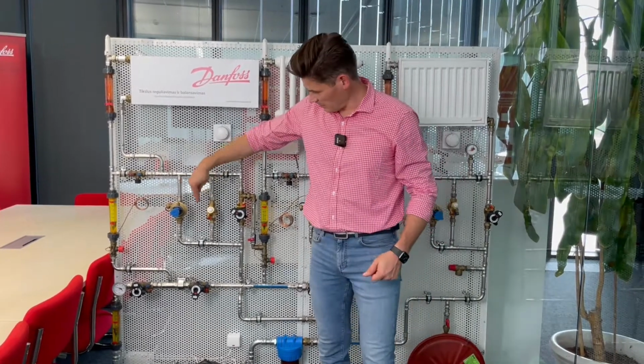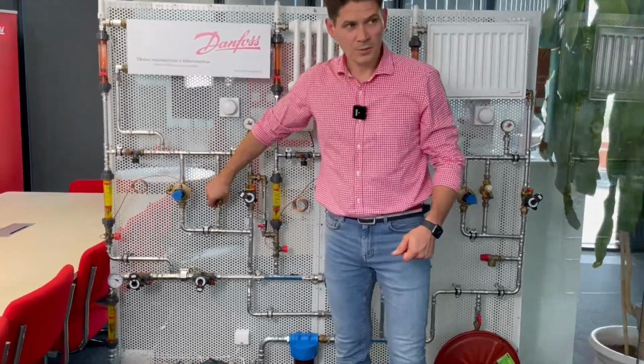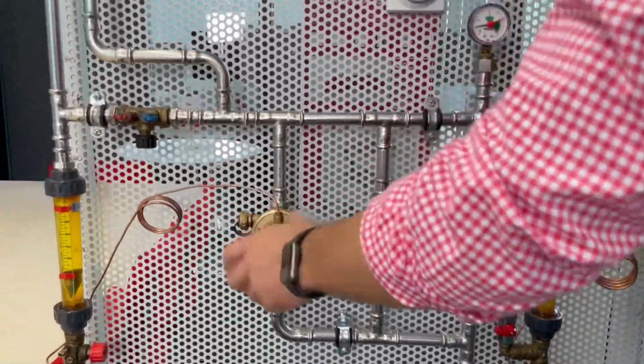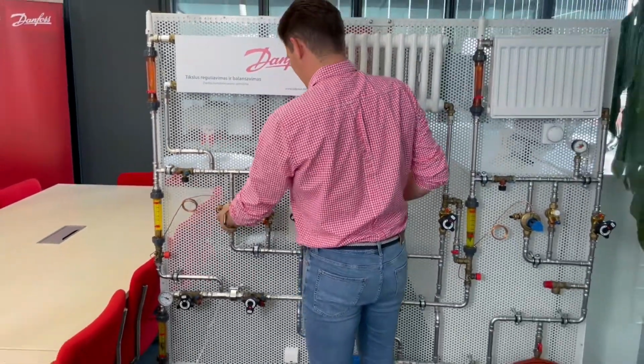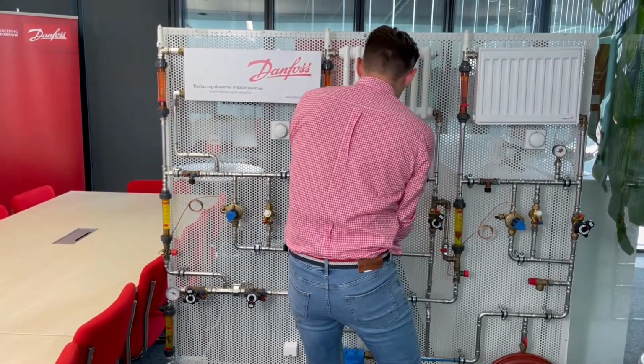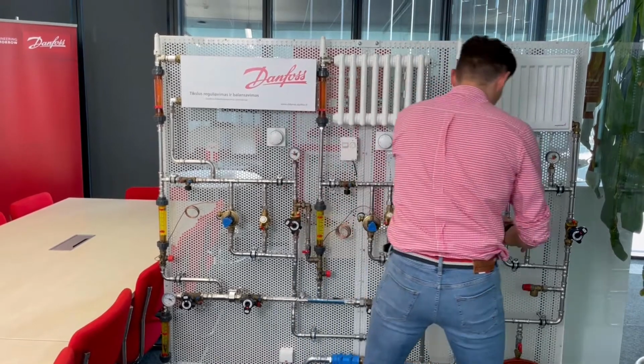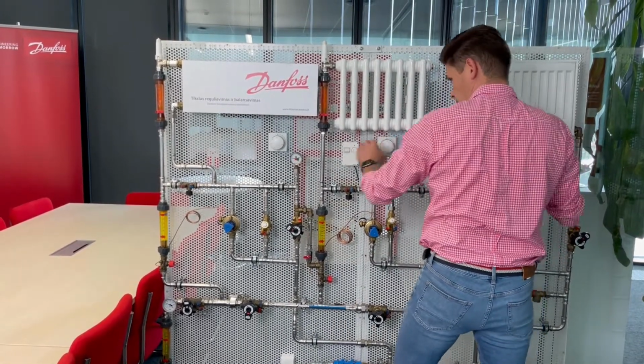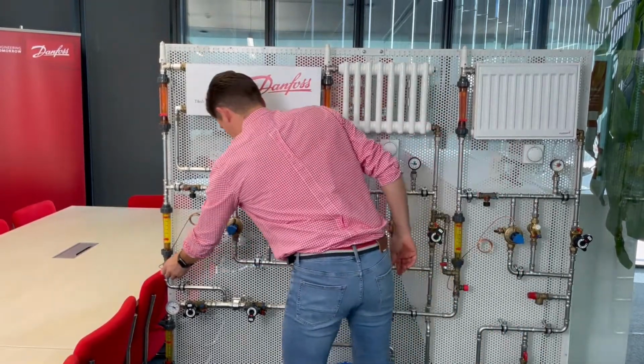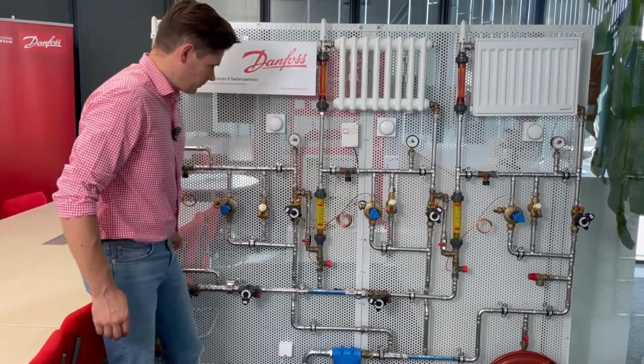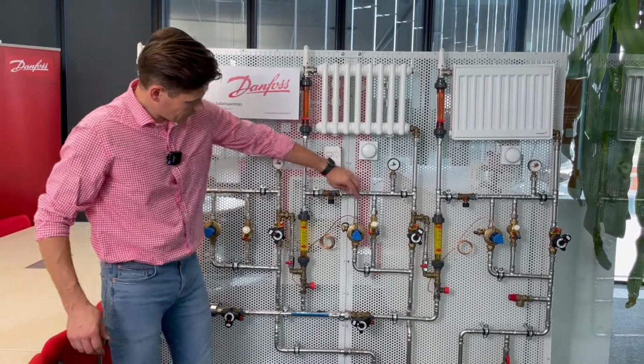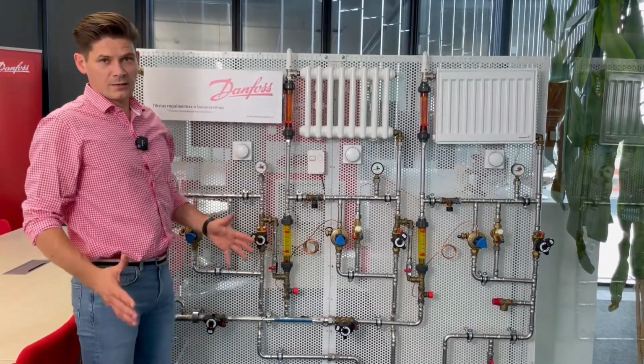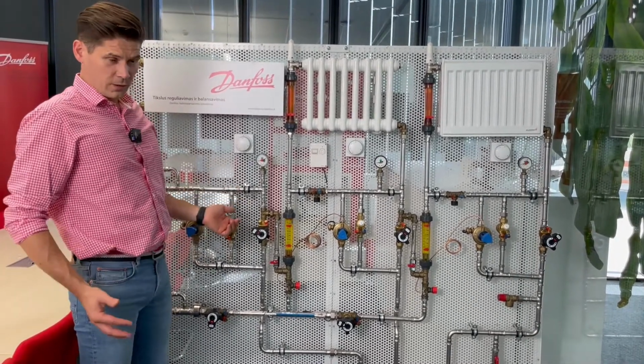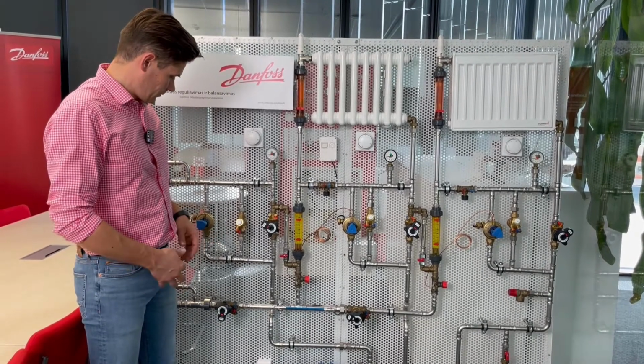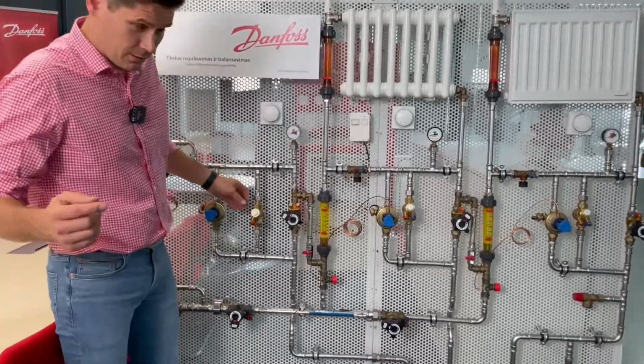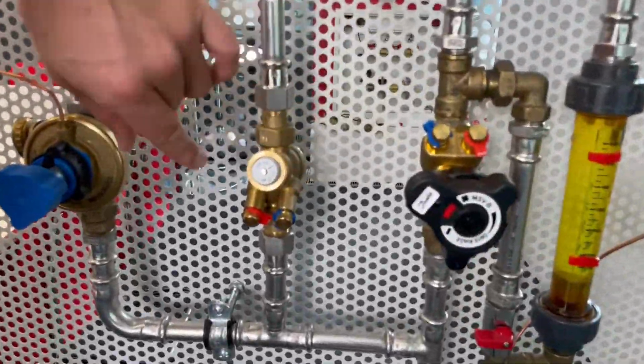Okay, the last automatic balancing valve is the ABQM, a pressure independent balancing and control valve. So I closed the pressure controllers, ASV-PVs, and I just leave them. Okay, just open this one, this one, everyone is open. I can now switch off the circulation pump, because for commissioning a system with ABQMs, or pressure independent balancing and control valves, we don't need to see flow. We can set flow without flow. And let's bring the camera closer. Here I will show what we have.